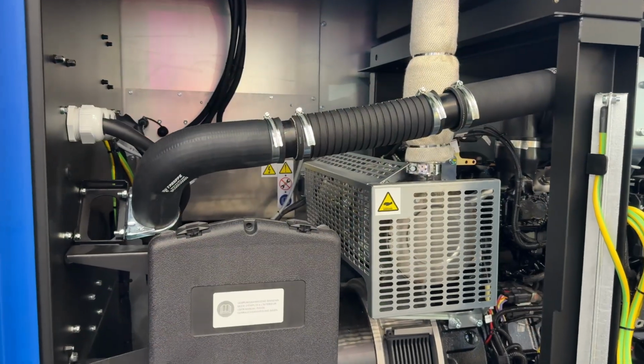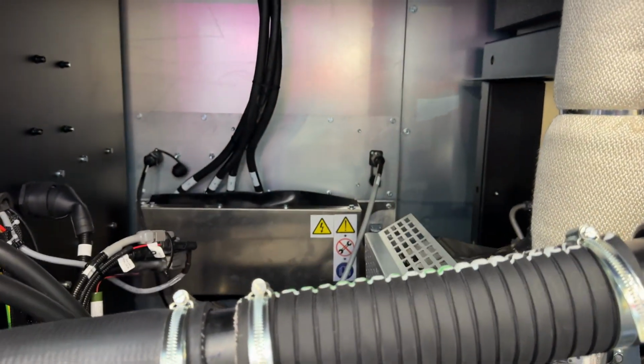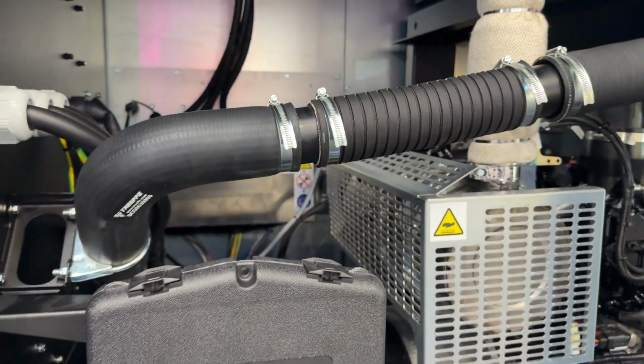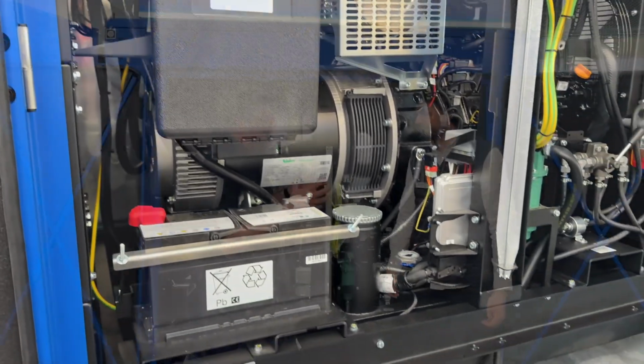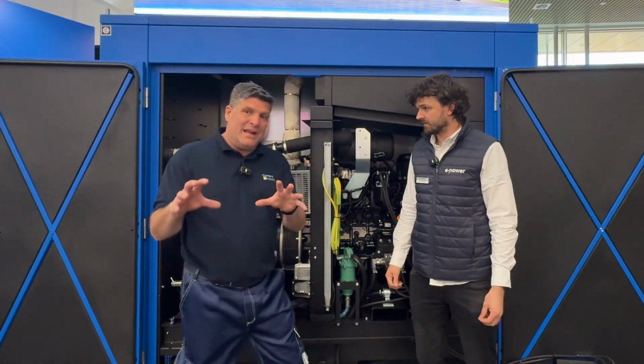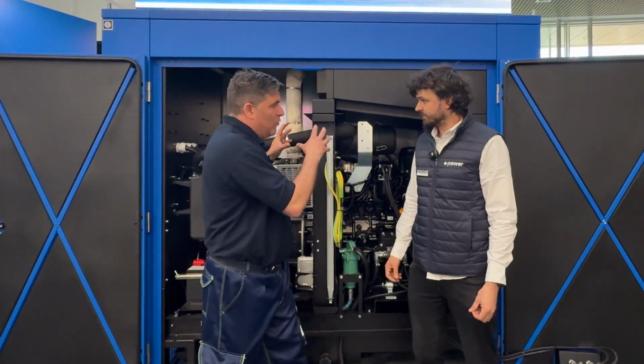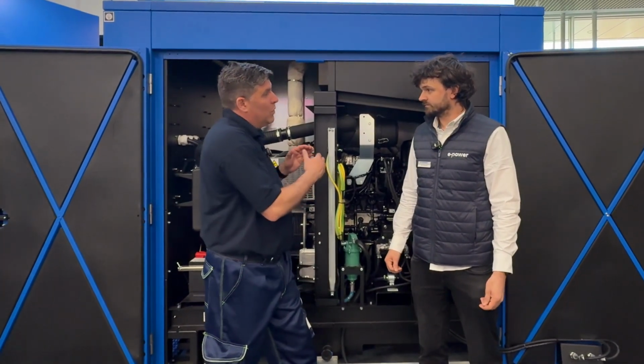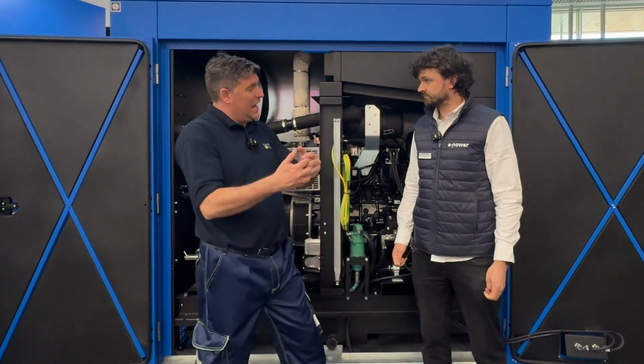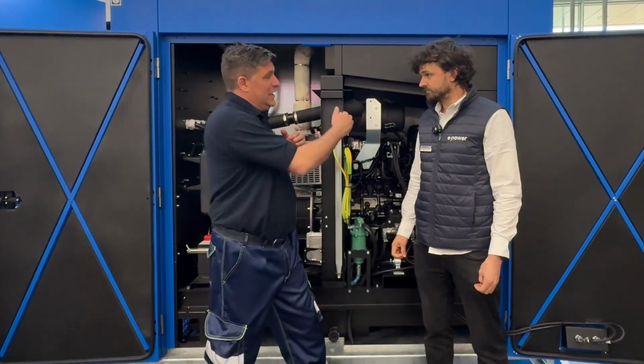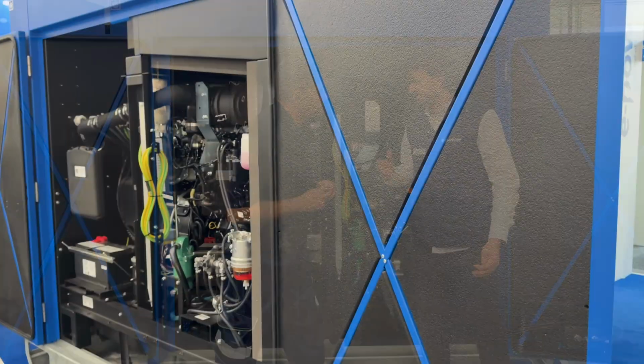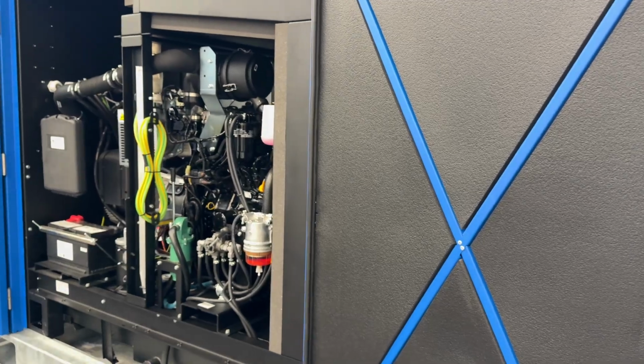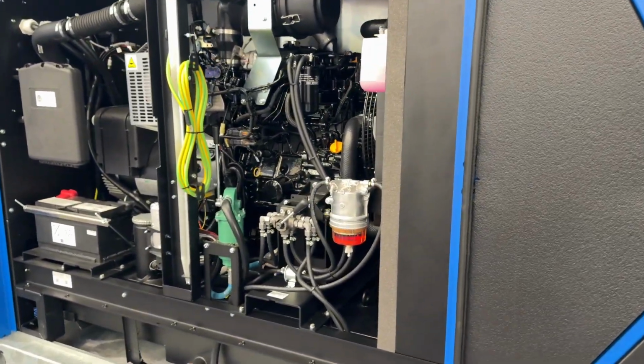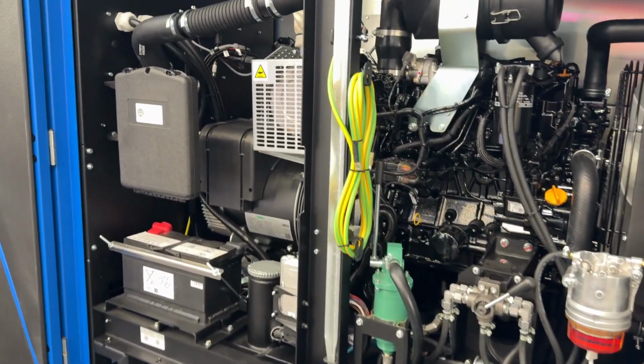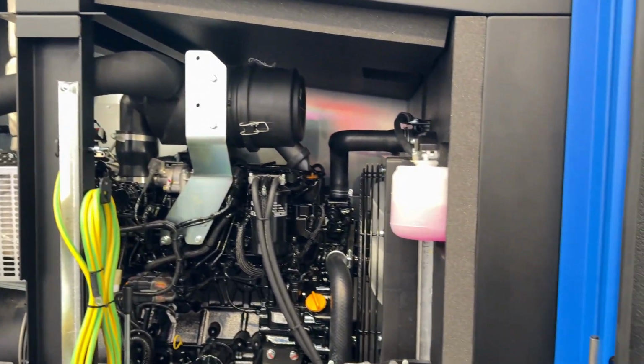Tom, we've come to the other side of the P-Grid, and this is the generator that matters when it's putting in the power. This is also about managing a microgrid, using the optimized nature of the generator to feed the batteries as well. You're running the unit from the battery, and if the state of charge goes down, the generator will start up.